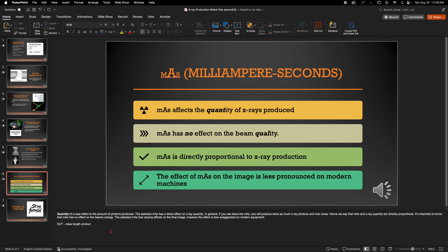This means how much dose is given over the length of the body part that we're irradiating. All right, so just to cover that whole thing again, mAs is not used the same way in CT as it's used in X-ray. In X-ray, you select the mA and the time, as in say 400 mA at 0.05 seconds, and you don't select time as much in CT.